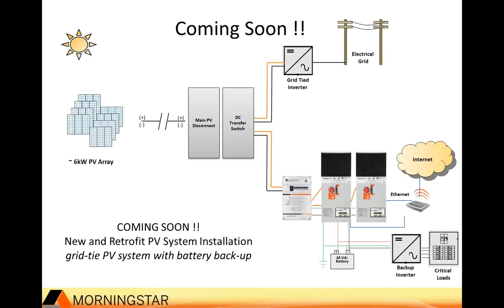Okay, a couple additional features that are coming soon for this product. The product is being released now and will be available starting at the first week of December for shipping. Some additional features that are going to be added shortly after that, I wanted to talk about quickly. One is we are going to be offering a DC transfer switch that can be connected to the solar PV input of the controller. If you have an existing grid tie system, this DC transfer switch would give you an easy way to switch the array from a grid tie inverter over to the 600 volt MPPT. So if you had an existing grid tie system and you wanted to utilize that array untouched for battery charging, you can do so with this transfer switch. Okay, so that's something we're going to be offering.